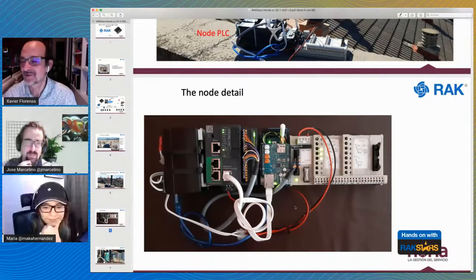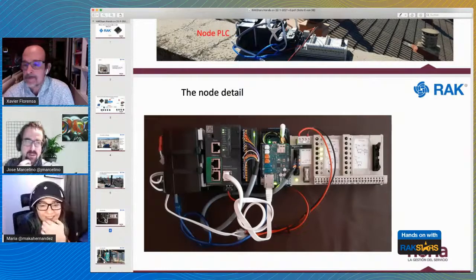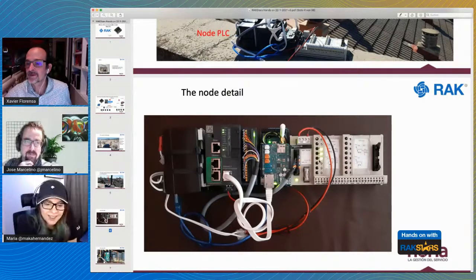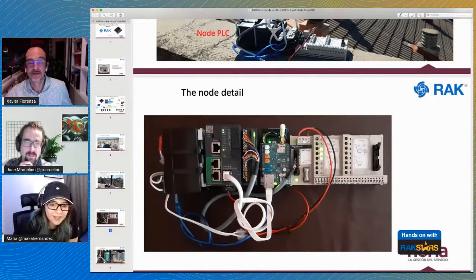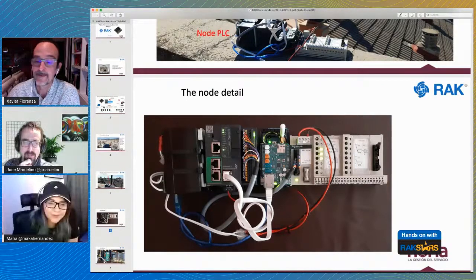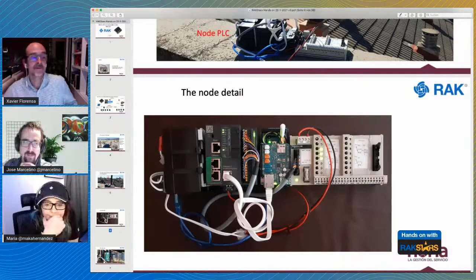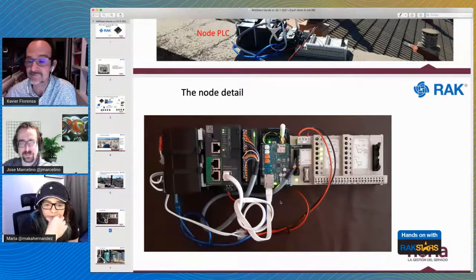With three floors. So you do the Modbus TCP on the Arduino? Yes. Here you have the digital inputs cabled in parallel to the digital inputs card of the PLC, and the program of the PLC, written in ladder logic under Codesys, gets all the digital inputs, packs them in 1 byte or more, and then sends per Modbus TCP with this patch cord to the Ethernet port, running on the Arduino running the Modbus library and LMIC. And then with LMIC we send again.